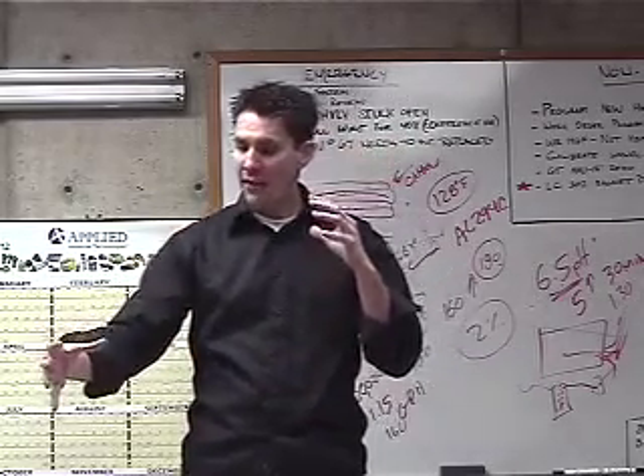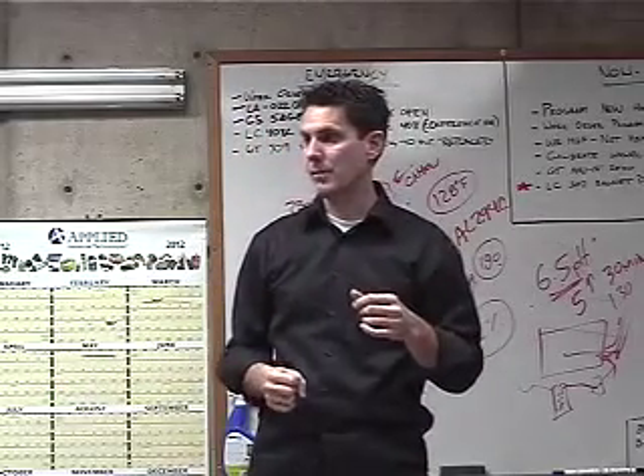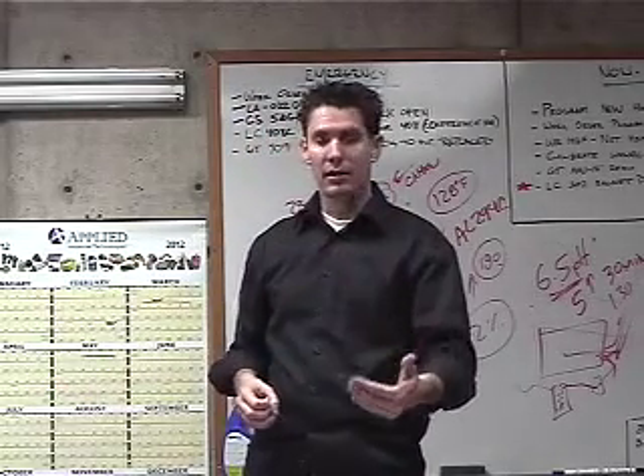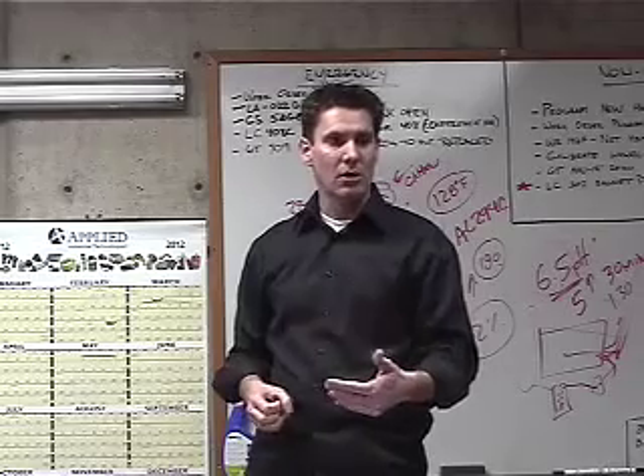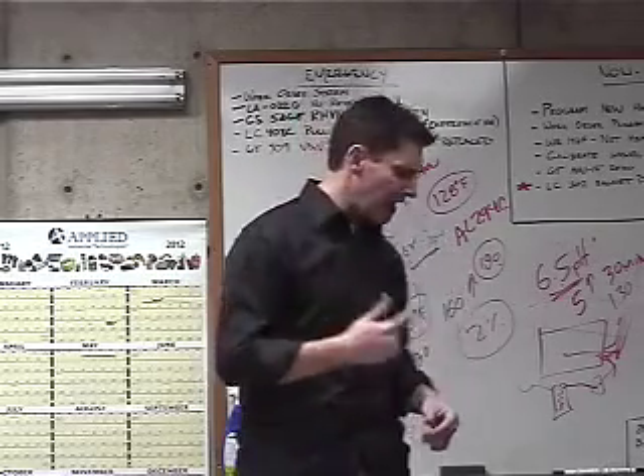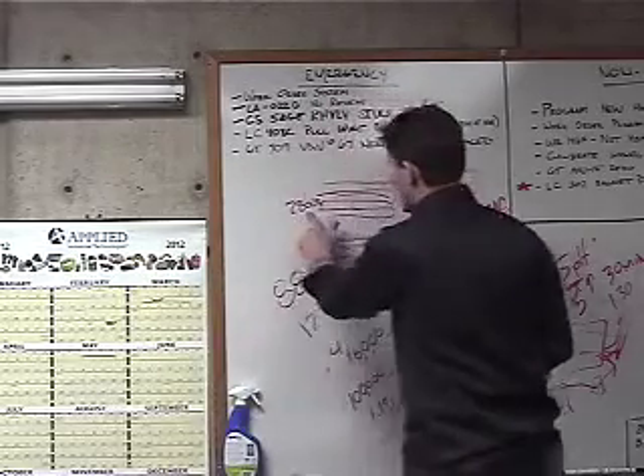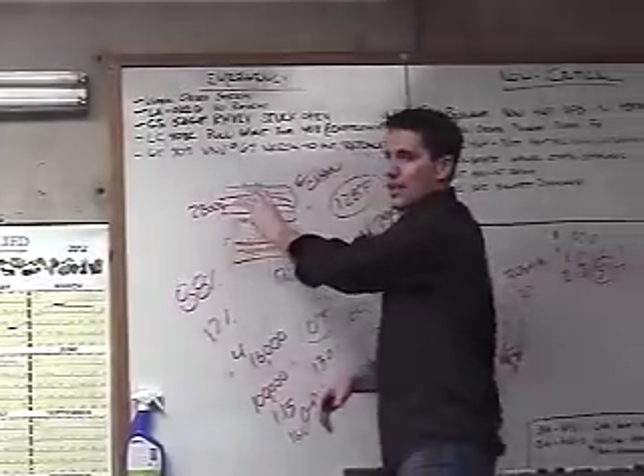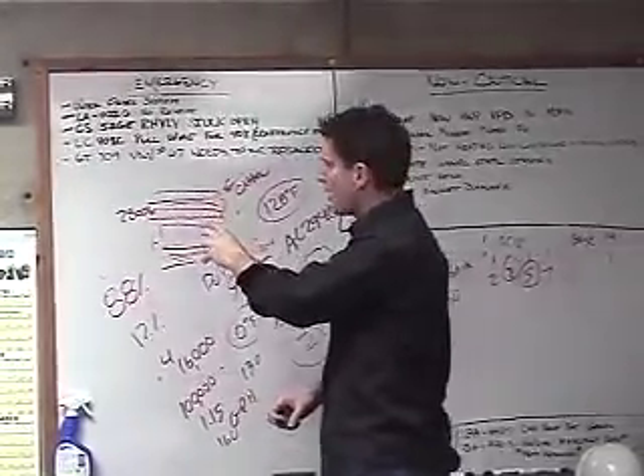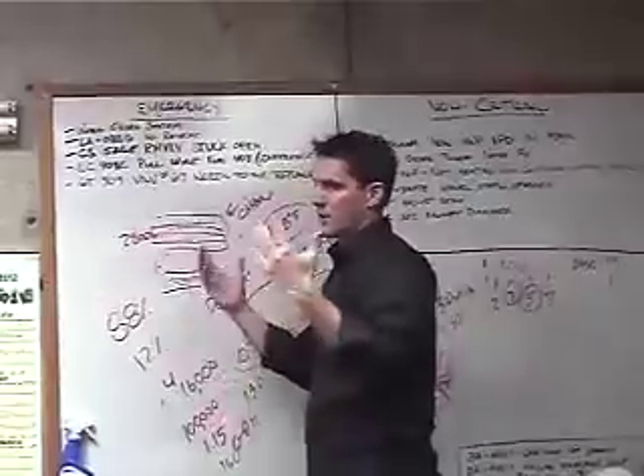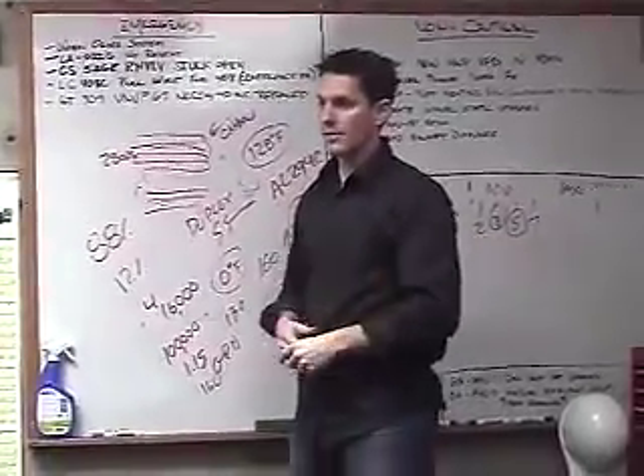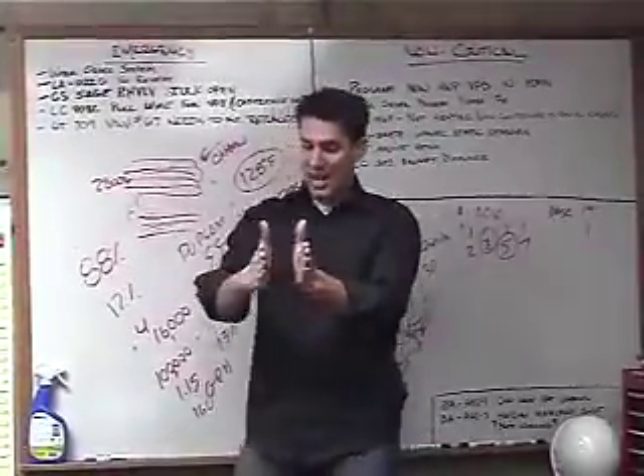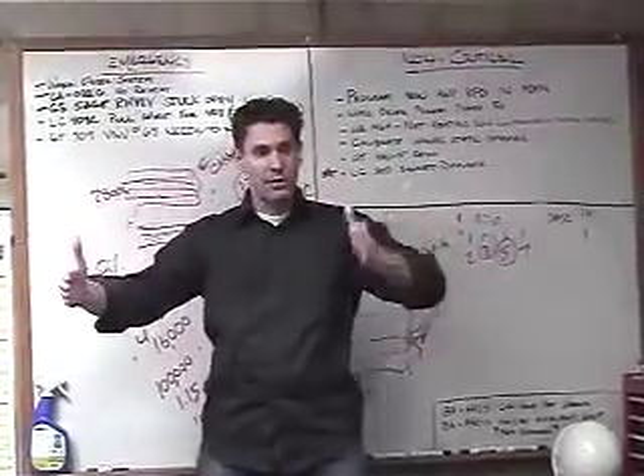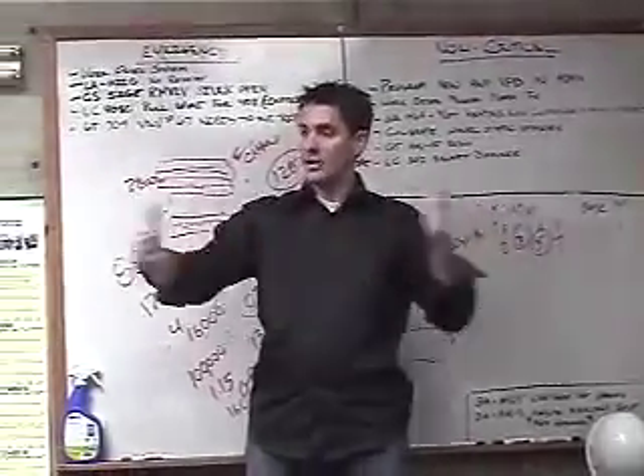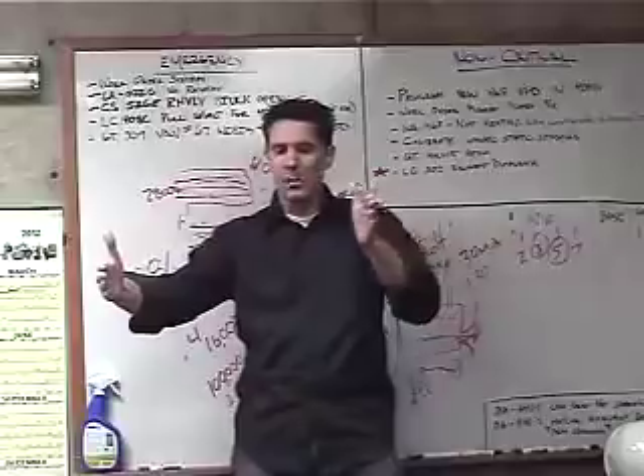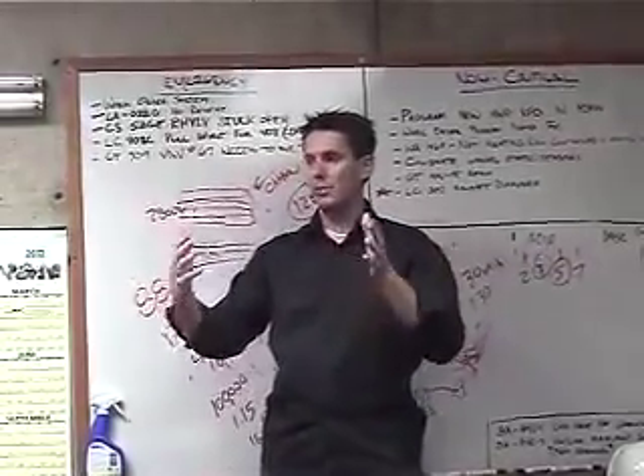We might now be having too much air through the process of combustion. So we're going to run lean. Okay? As we run lean, what's the dangers of running lean? I didn't really go over this, but we're trying to shoot for about 2,800 degrees Fahrenheit. Okay? And then the reason we want this, our flame temperatures could be around 3,200 degrees, 3,400 degrees Fahrenheit. The hotter the flame temperature, again, the bigger that gap between my water temperature and my flame, so I have more heat transfer available. But I've got to cool my flame temperatures down so I prevent pollutants.